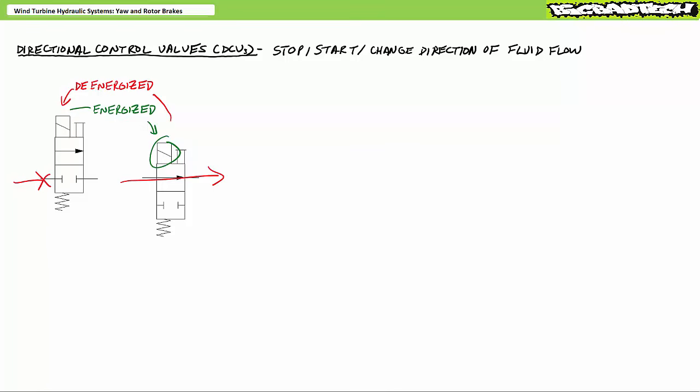left to right. Since there may be occasions in which the controller, electrical signals, conductors, or solenoids themselves may be damaged or non-responsive, certain directional control valves may offer a means of directly shifting the valve to the actuated position via a manual override. A manual override might take the form of a plunger that's pushed in or pulled out, a lever that's pulled up or pushed down, a screw that's screwed in or screwed out, or some other means that's diddled or dorked with, effectively forcing the valve into the activated position. The top hat symbol identifies this valve as having a manual override that can force the valve into the straight-through position and keep it there if the solenoid is ever out to lunch.